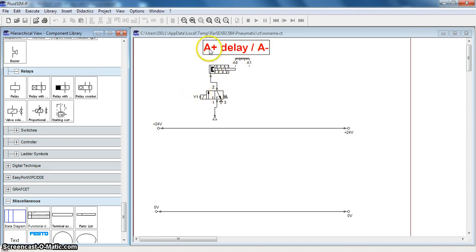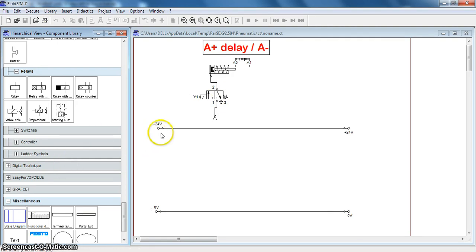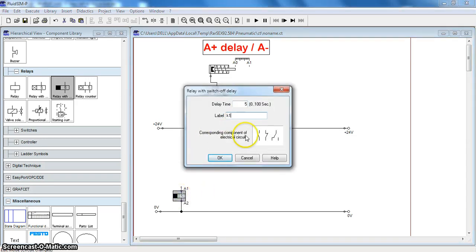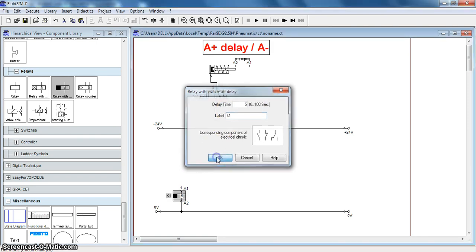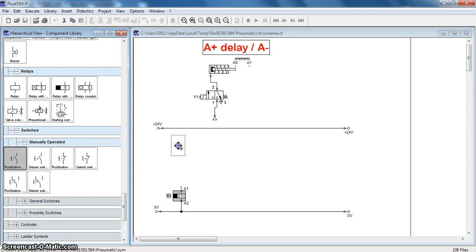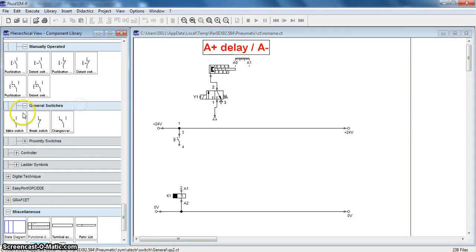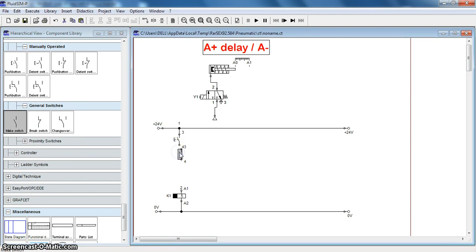This part is powered by solenoid Y1, whereas this part will happen by the action of the spring. Now to draw the pneumatic circuit we will take a delay here. We will name this as K1 relay and the delay time is 5 seconds. We will use a start button here, a push button, and connect this to the circuit. Then at the end of the circuit, A0 will be initially on, so we will put a normally open contact which we will name as A0.